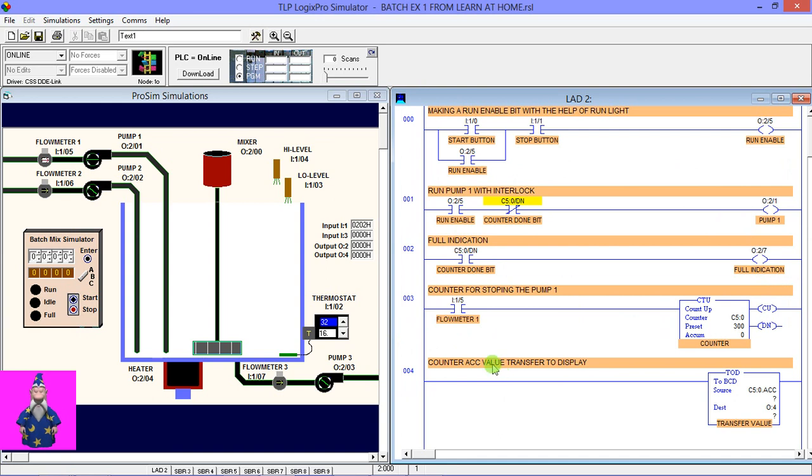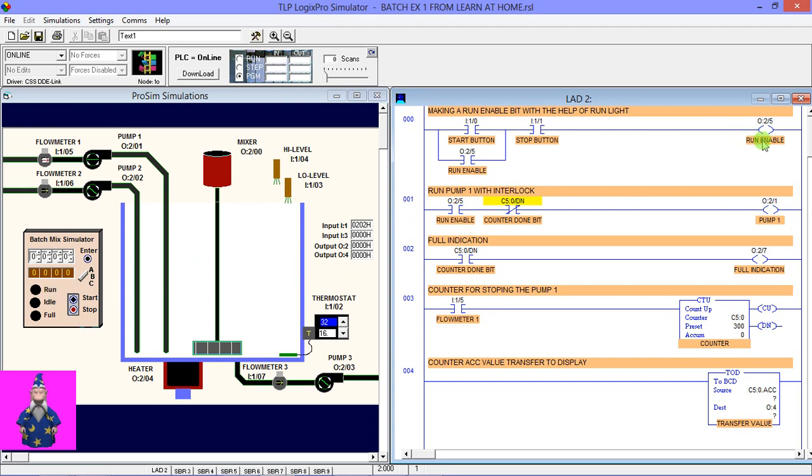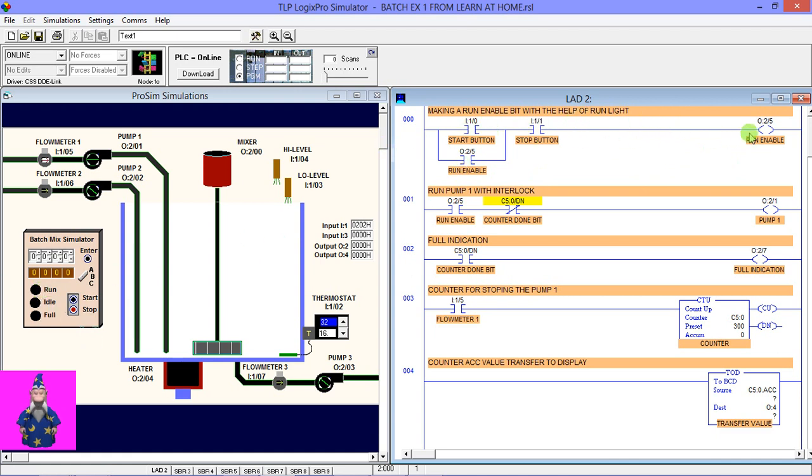Here, when I press the start button, you can see in the first rung, by pressing the start button, I can make this bit enabled. Here you can see this run enable bit. I made this with help of the run LED output. This output is used for making the run enable bit. So I saved one rung. If I use here a binary bit, I have to give another rung to make this light energized. So I use this light. This start button will also energize this run LED and also make a run enable bit. And for the stop function, I used a stop button here. This is a holding.